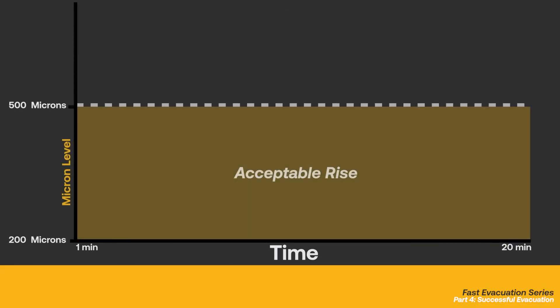If the system stays within the acceptable rise for the full duration of the decay test, this proves that the system is clean, dry, and tight, signifying the evacuation was successful.